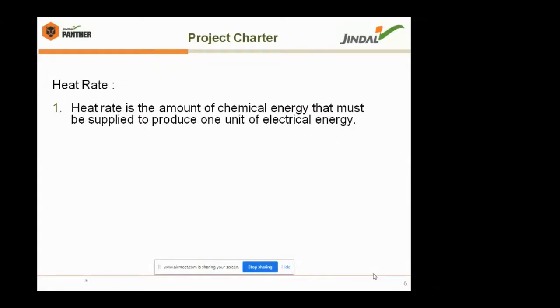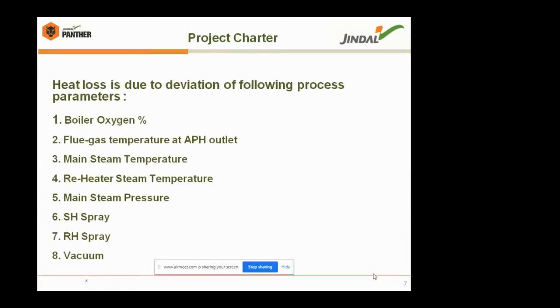What is heat rate? Heat rate is nothing but the amount of chemical energy that we are supplying to produce 1 unit of power. And the net heat rate is the heat which we are supplying to produce 1 unit of net power after reduction of auxiliary from the gross generation. Basically, the main reasons for heat loss are the following parameters: boiler oxygen, flue gas temperature at APH outlet, main steam temperature, reheater steam temperature, main steam pressure, superheater spray, reheater spray, and vacuum.